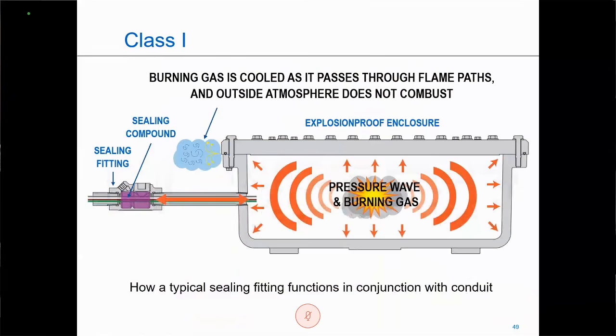Essentially, this unit is going to contain the explosion. The flame path is going to allow those cool gases to escape, and the explosion is going to want to be traveling in our conduit, and this sealing fitting is going to make sure that it doesn't continue to travel down. It's going to minimize the effects of those gases and vapors.